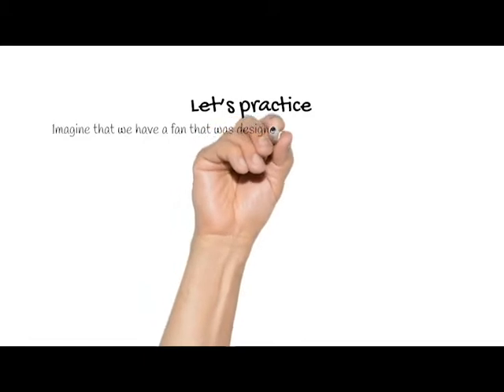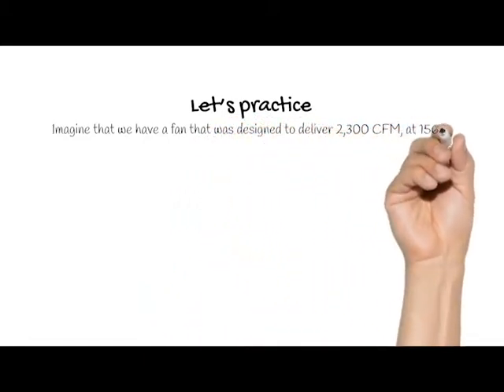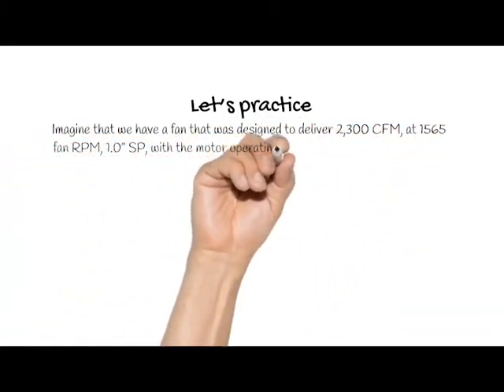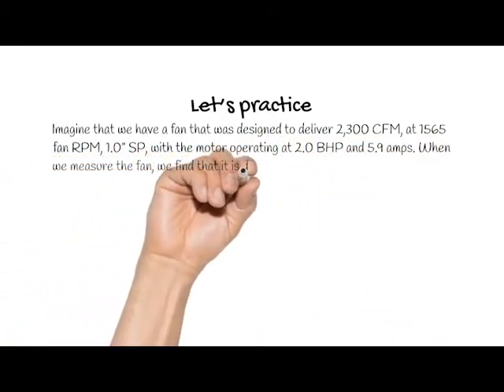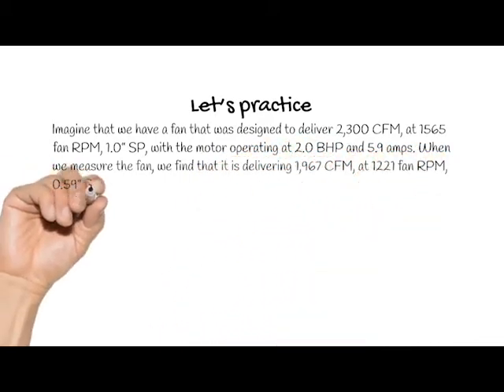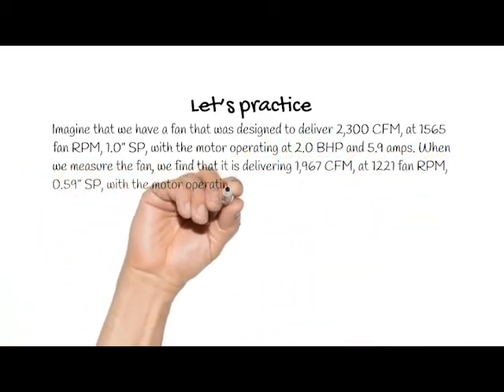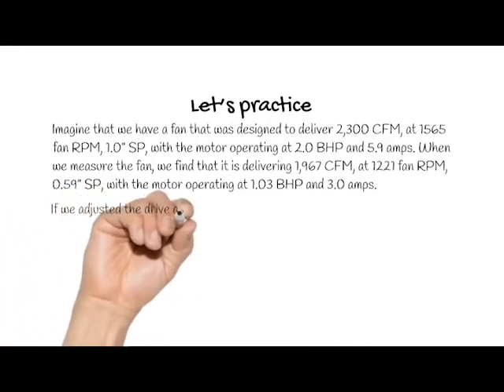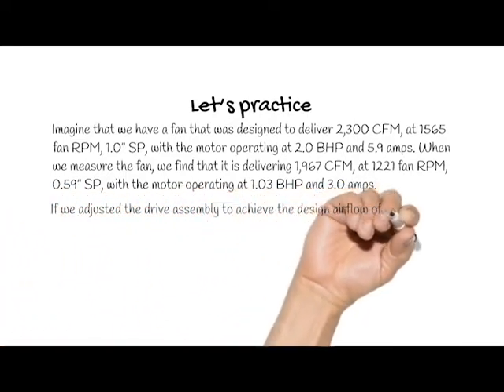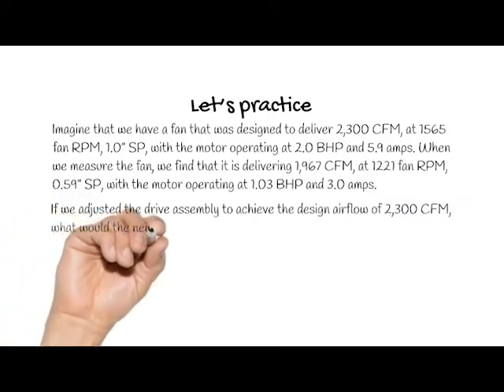Let's practice. Imagine that we have a fan that was designed to deliver 2,300 CFM at 1,565 fan RPM, 1.0 inches static pressure, with the motor operating at 2.0 brake horsepower and 5.9 amps. When we measure the fan, we find that it is delivering 1,967 CFM at 1,221 fan RPM, 0.59 inches static pressure, with the motor operating at 1.03 brake horsepower and 3.0 amps. If we adjust the drive assembly to achieve the design airflow of 2,300 CFM, what would the new operating conditions be?